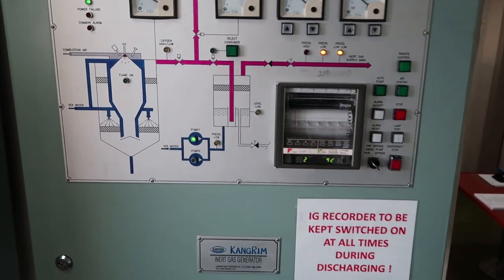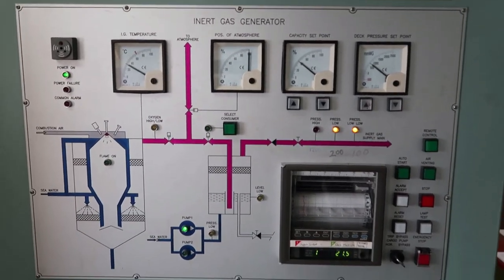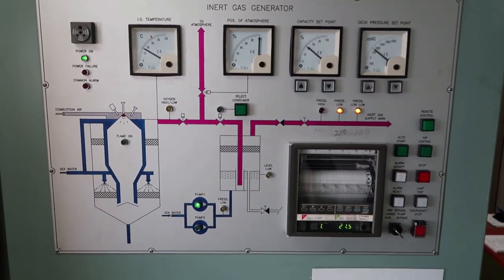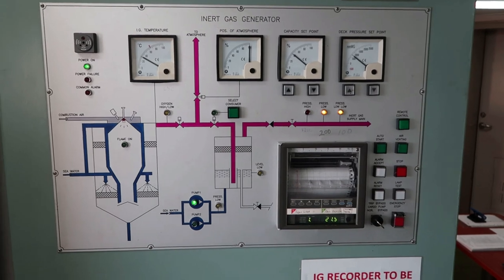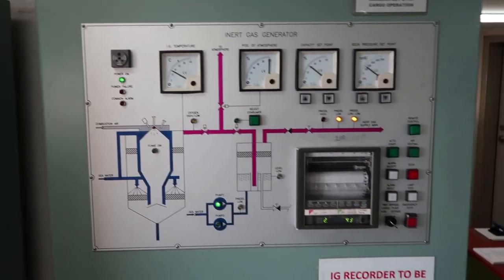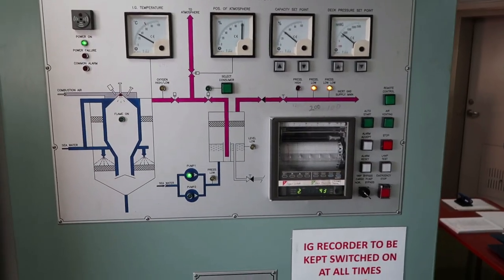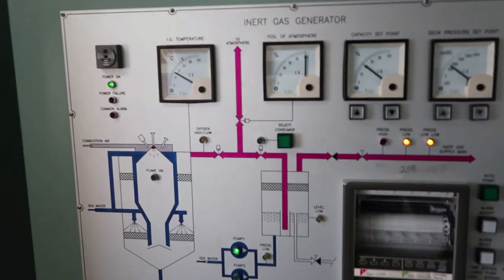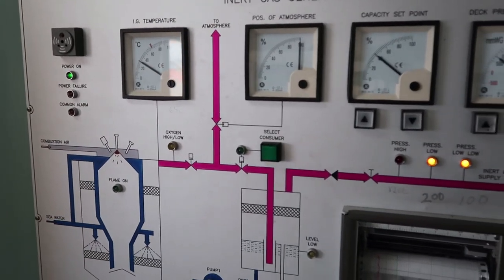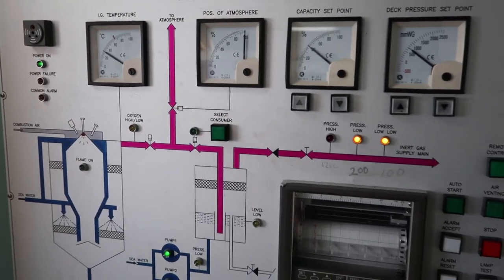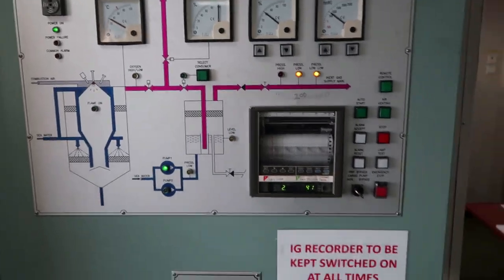When you cross 11% oxygen that is the time when you will cross the flammable range. But safety margin of 3% is given and we are supposed to have at least less than 8% oxygen content in any of the tank.